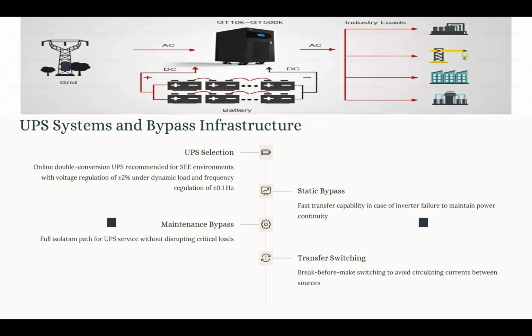We have to have a fast transfer capability in case any of the sources are failing. We have to have full isolation paths for UPS services so we don't disrupt the critical load supply. And we have to have a transfer switch with break-before-make switching to avoid circulating current between the sources.